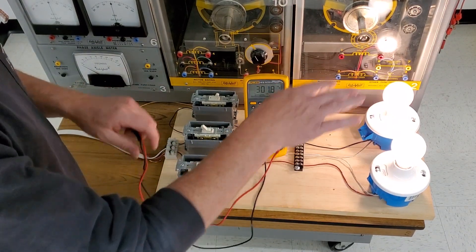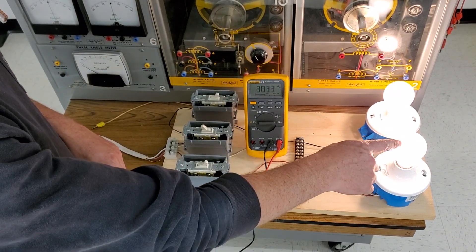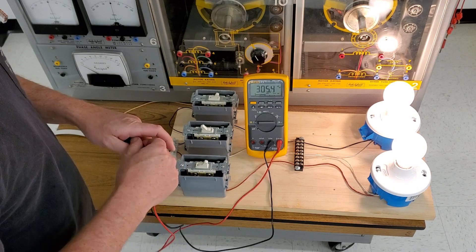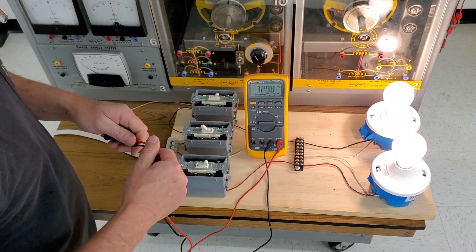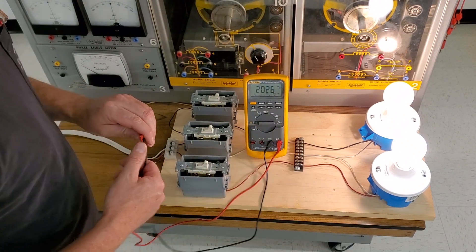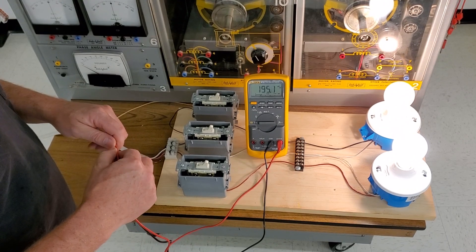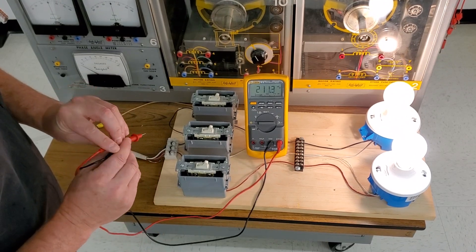So always be careful when you're in a multi-wire branch circuit that if you lose your neutral, you put your loads in series. And I've seen this happen on the job site.